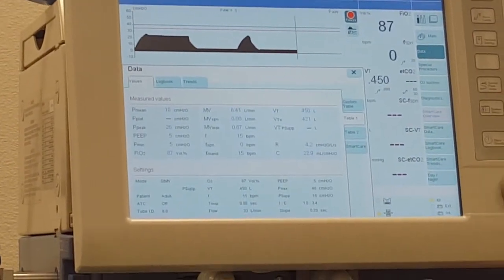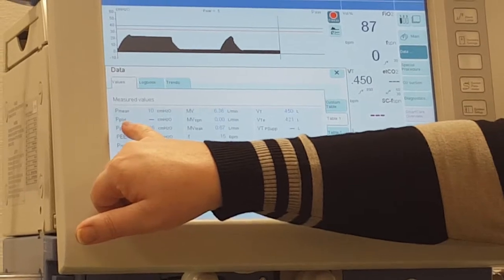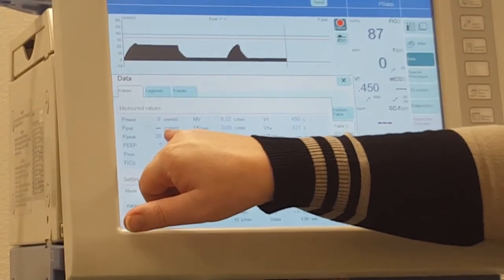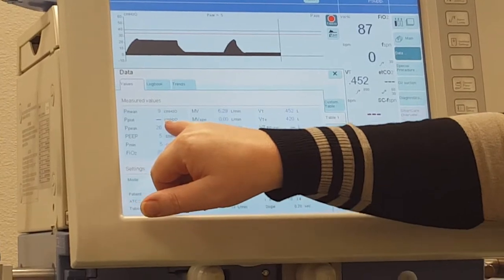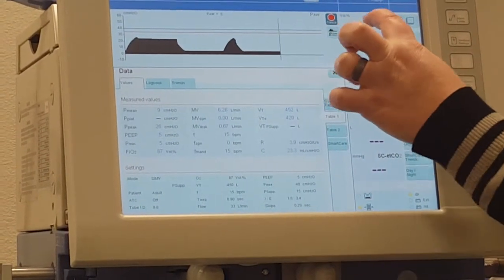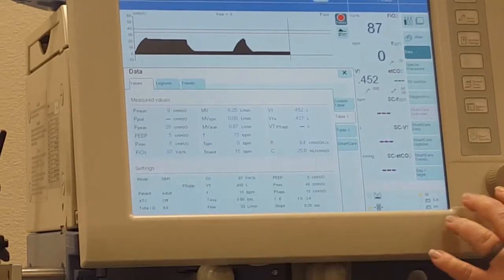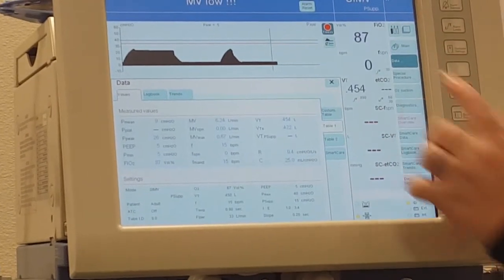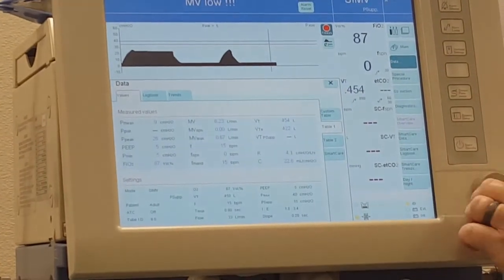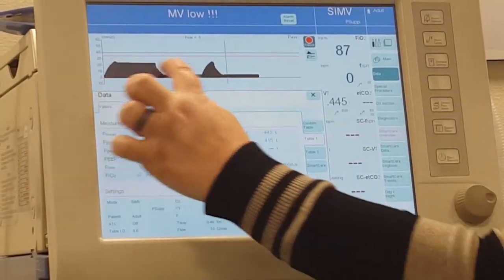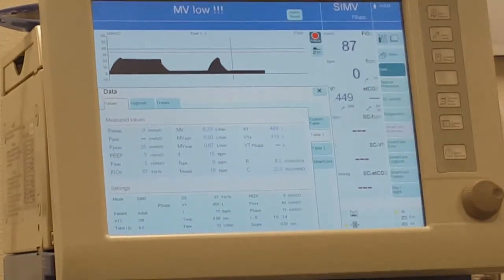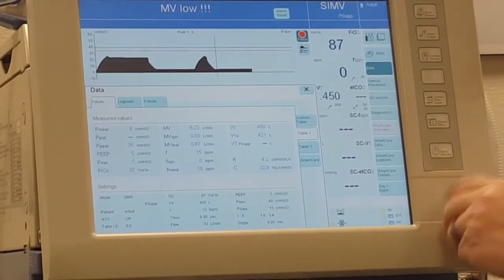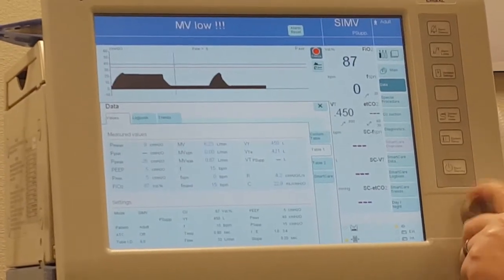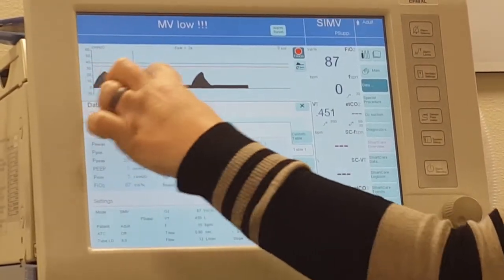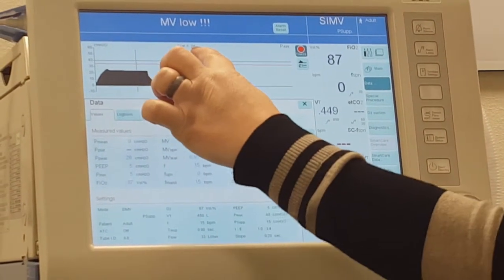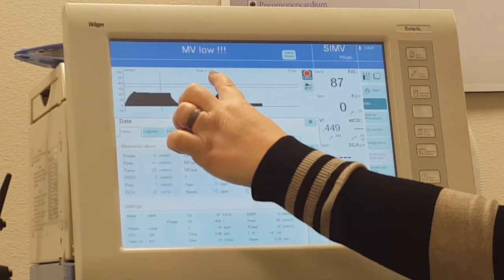Oh, here we go. Here I went to table 1. You'll see right here, the plateau says nothing. It's not even there for me to get. So what I can do is I froze my screen as soon as I did it. So if you don't see it here, what you do is once your screen is frozen, take your dial, and you'll see this blue line move. Take your dial, and you're going to go all the way over to here where the flat spot is, because the flat spot is where we did the inspiratory hold. And so we're going to go all the way over to here. And once your line is in any place on the flat spot, check and see what this number is next to PAW, and that will be your plateau reading.